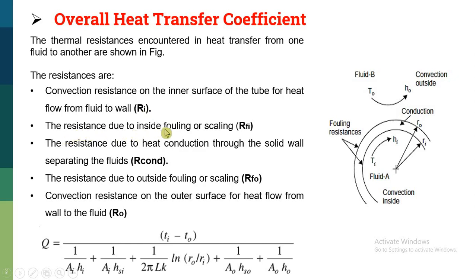The next resistance is due to inside fouling — whatever deposits are present in the hot fluid get deposited on the inside surface of the tube — and we consider the fouling factor RFI. The next resistance is due to conduction through the solid surface wall. This tube is made up of a solid material such as aluminum, copper, or steel, and heat transfers from one surface to the other by the phenomenon of conduction. So we have to consider the conduction resistance.